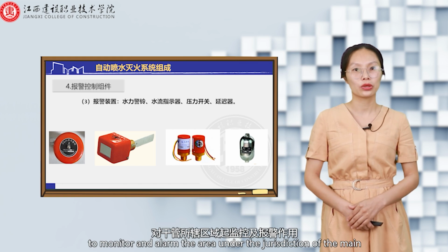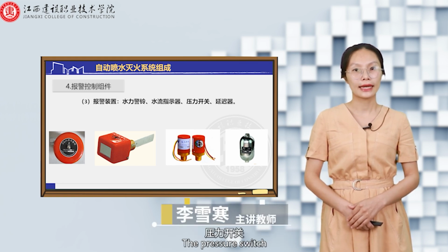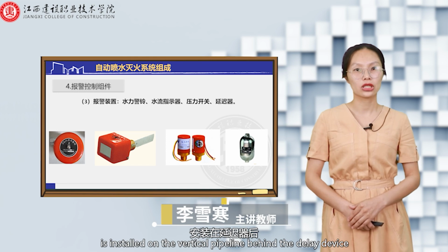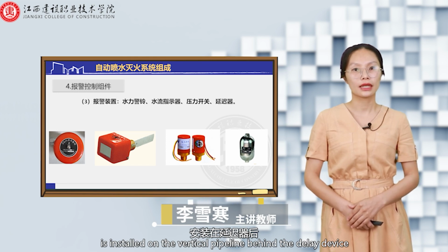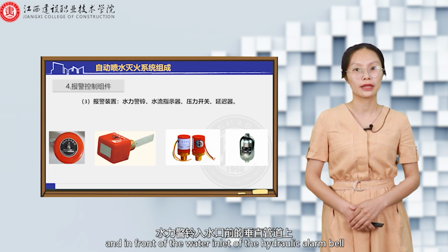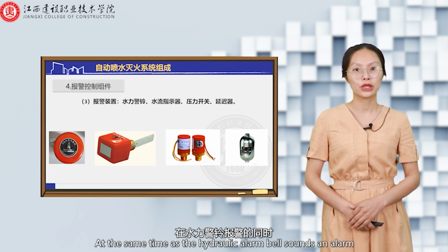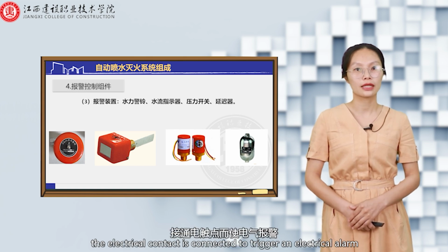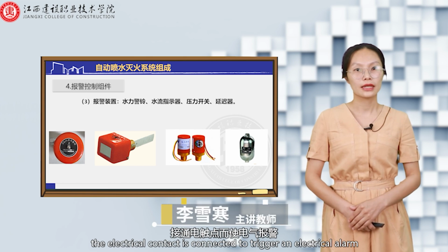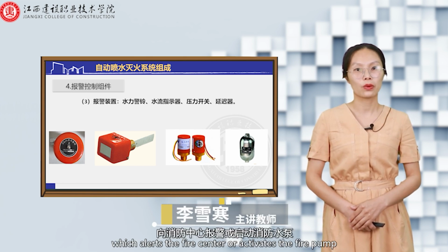To monitor and alarm the area under the jurisdiction of the main, the pressure switch is installed on the vertical pipeline behind the delay device and in front of the water inlet of the hydraulic alarm bell. At the same time as the hydraulic alarm bell sounds an alarm, the electrical contact is connected to trigger an electrical alarm, which alerts the fire center or activates the fire pump.